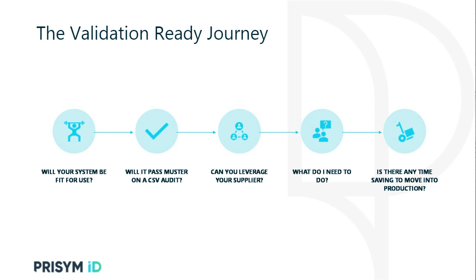So essentially this is deploying a system which has all the objective evidence required, which is based around the GAMP5 guideline. They're ready for you. All the functionality testing done, results and reports available and transparent, so you can move forward with the final stages of validation based on risk, with confidence that the functional testing has been completed.